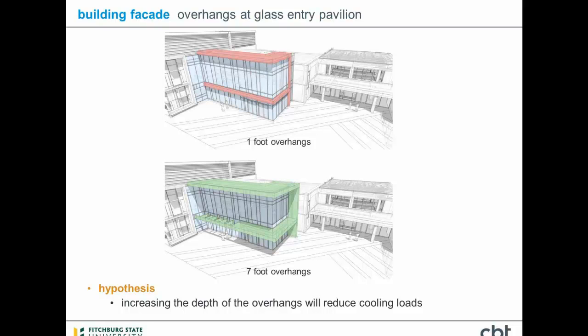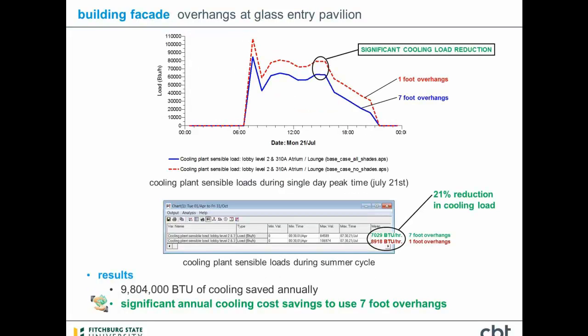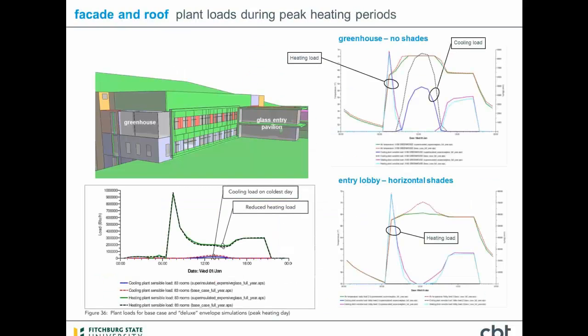So we looked at a series of different overhang configurations, ranging from 1-foot overhangs up to 7-foot overhangs, to see if we could justify the additional expense by way of any savings that might be realized. And what we found was that between a 1-foot overhang and a 7-foot overhang, there actually was a fairly dramatic reduction in the cooling loads on that side. We were able to reduce the cooling loads by 21%, which represented a significant cost savings to the university. On a related note, here's that glass entry pavilion that we talked about that we modeled specifically for looking at the overhangs.